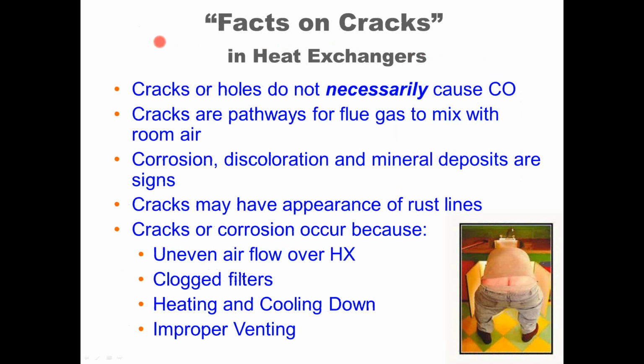So in our summary here on heat exchangers, facts on cracks: cracks or holes do not necessarily cause CO, but because they interfere with the airflow or can interfere with draft, they could actually cause CO. They may not necessarily cause it, but they could cause it. Cracks are definitely pathways for flue gas to mix with the room air, or vice versa, room air to mix with the flue gases. You might not think that's as important, but say you have an induced draft furnace and it's looking to pull so much air, at such and such a pressure with its pressure switch. If it's pulling air from the distribution air or the room air side and it's not coming through the combustion system, it may be interfering with the amount of combustion air coming through because it's pulling air from the distribution air side. It's kind of a little advanced topic here, but leaks both ways can influence the system. It's not just a one-way leak that can be dangerous.